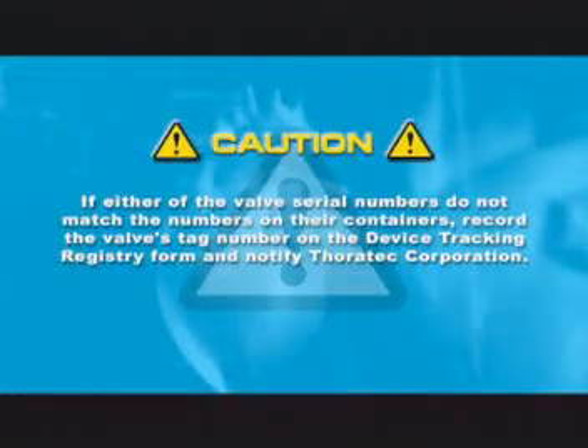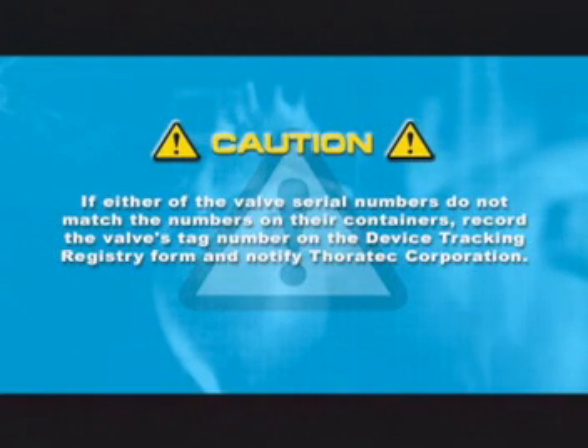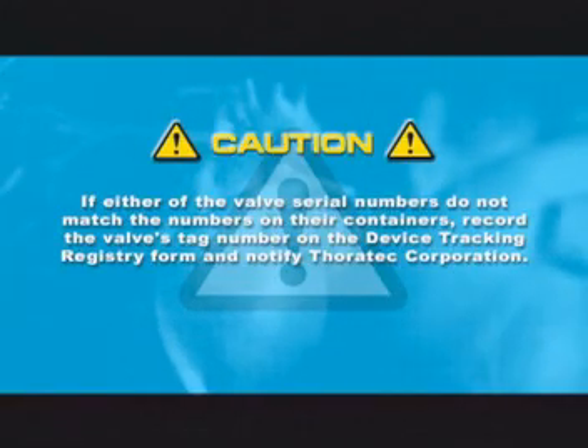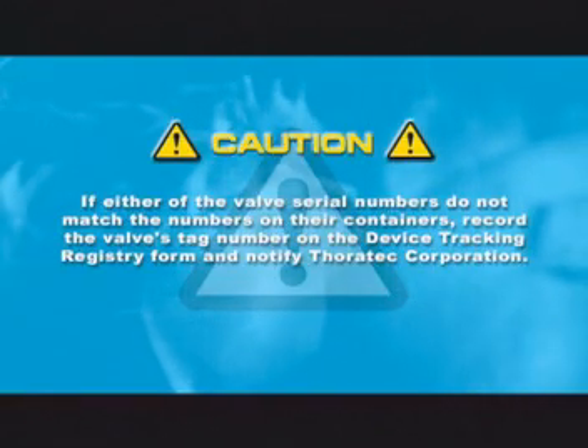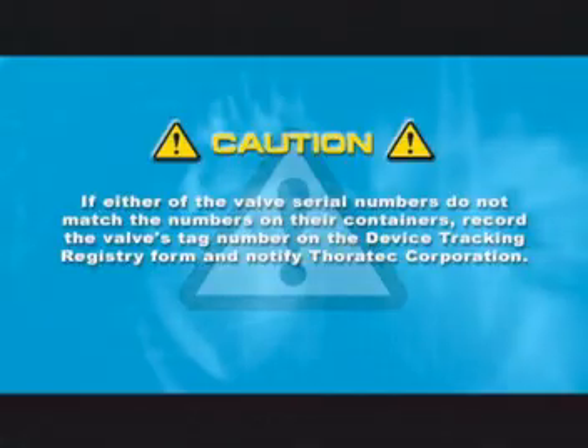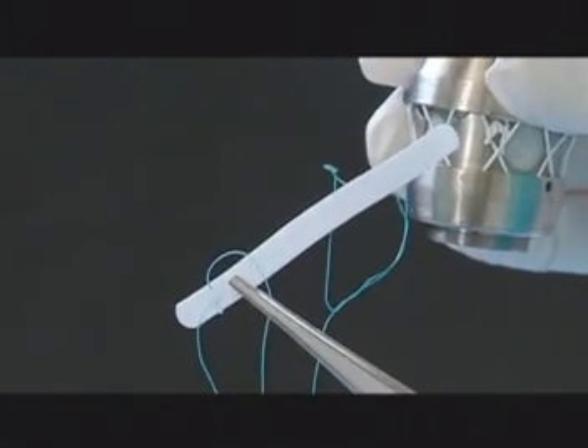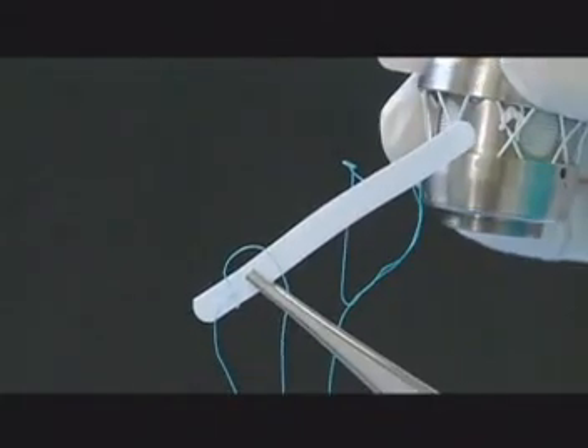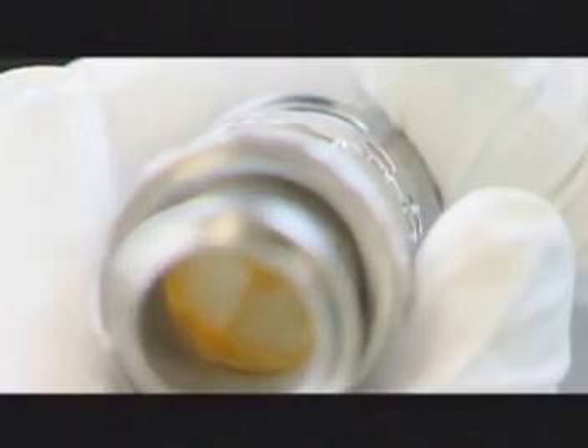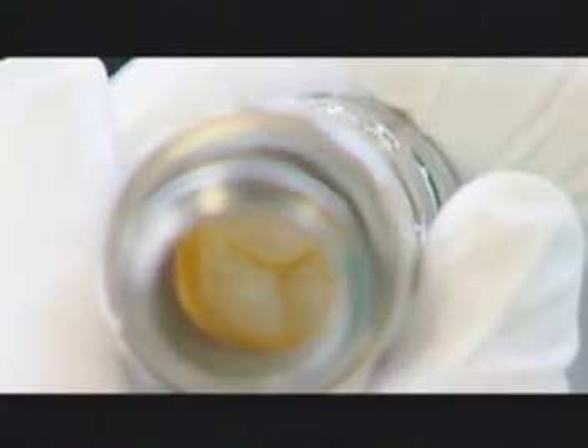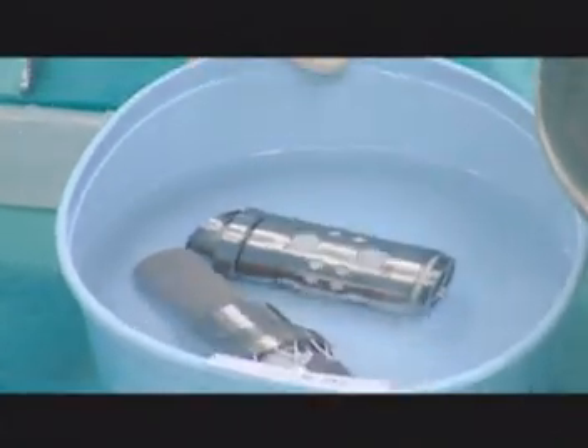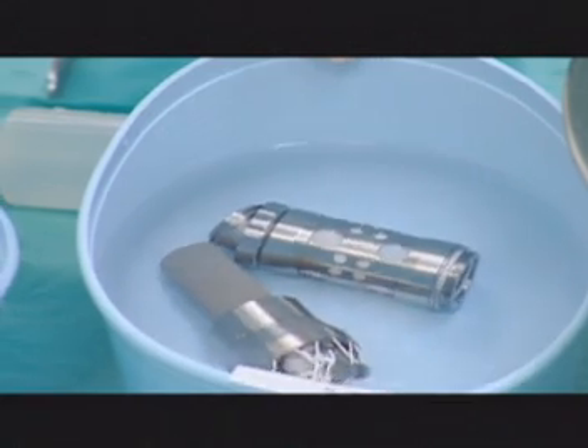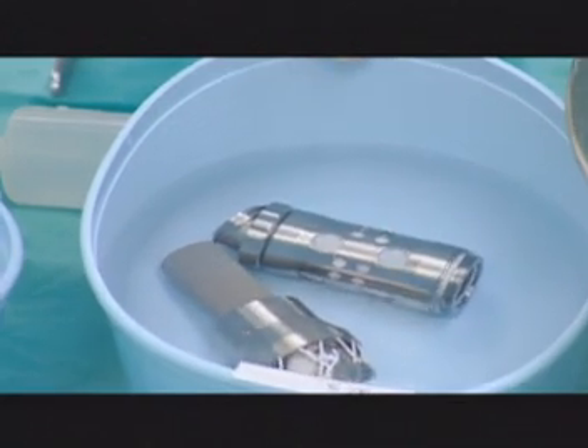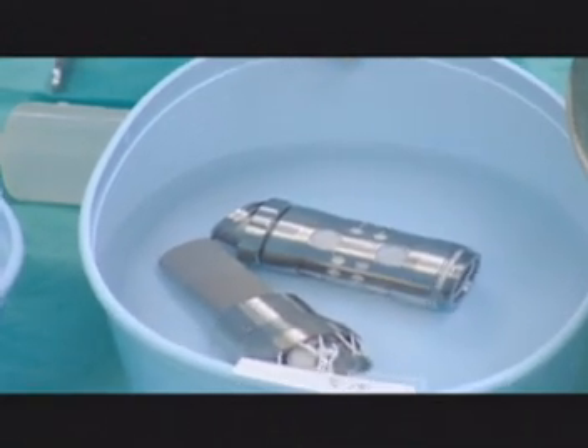Caution: if either of the valve's serial numbers do not match the numbers on their containers, record the valve's tag number on the device tracking registry form and notify Thoratec Corporation. Remove and discard the white serial number tags on both valve conduits. Next, assess the integrity of the tissue valves by examining them closely. Both valve conduits should then be placed into the first basin of sterile normal saline solution, rinsed and gently agitated for 10 minutes.